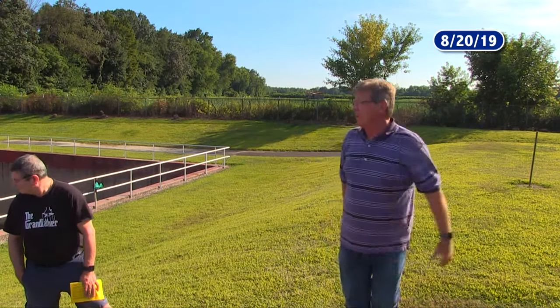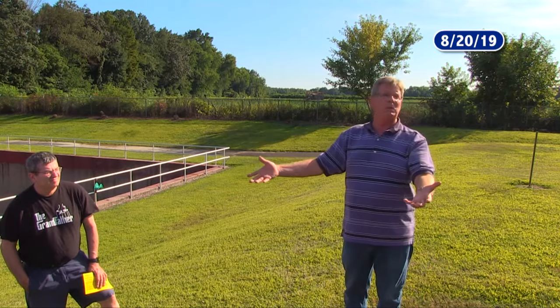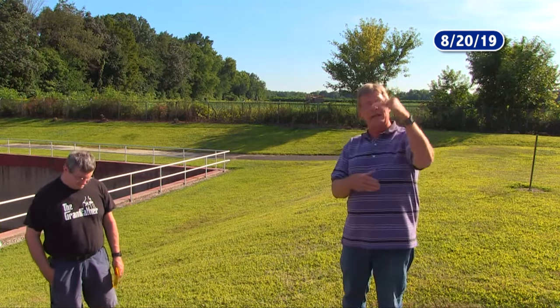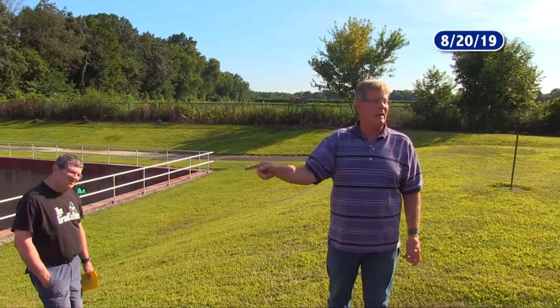And if we went with a diffused air system, you wouldn't have this egg beater that makes a bunch of noise and tosses your process up into the air in the winter time into 5-degree temperatures, and then it cools the entire tank down. And when that happens, the microorganisms that do all the work slow down. Their metabolism slows way down. So then you have to increase your population to a high enough level that you make up for that a little bit. And now you're carrying this huge inventory of microbes that need oxygen. One wrong mishap with that thing, and all of a sudden you're out of commission and all those bugs are starving for air. And once you get past 24 hours, they're going to die. It all goes into a state of anaerobic condition, septic condition, and they'll all die, and now you've lost your treatment.